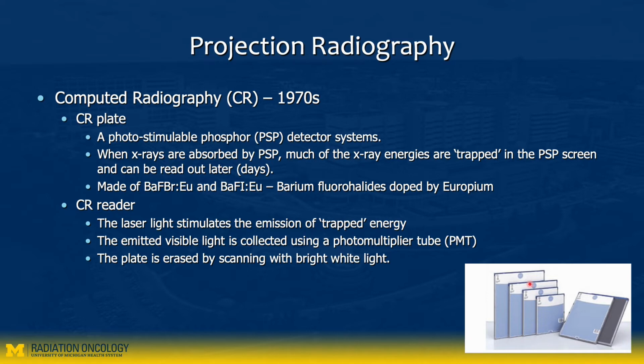This is not a film. It is actually a photostimulable phosphor detector system. You use this plate in place of film. When X-rays are absorbed by this phosphor, much of the X-ray energy is trapped, and then it can be read out later. It can be stored for days. So this is like a cassette.